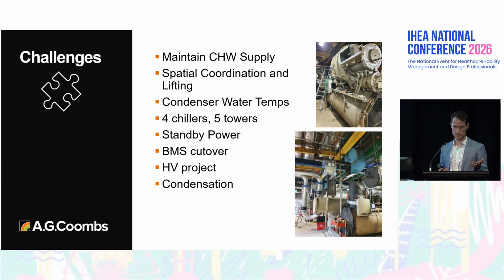We were reusing the existing condenser water cooling towers, but we had a change in temperature and had to get more capacity out of the existing plant, so that had some challenges. And because we had 4 chillers and 5 towers, the alignment of plant became a bit of a challenge and required some focus.